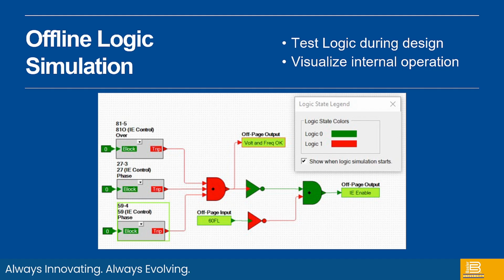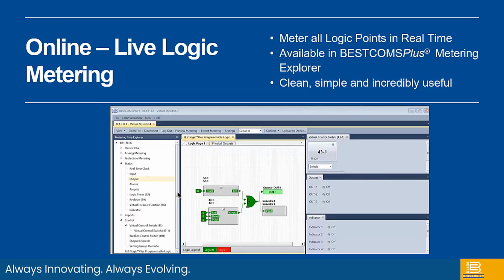In addition, we have the ability to do logic simulation. As you're creating the logic, you can click the Turn On Simulation button, and it'll show you the status. Because it's an offline simulation, if I want to manually operate, let's say an 81 over frequency, I would just double click the word trip and have it run through and see what happens in my logic. That's the offline simulation somebody would do, perhaps when creating a settings file, if they're trying to debug a settings file to make sure it's what they want it to be.